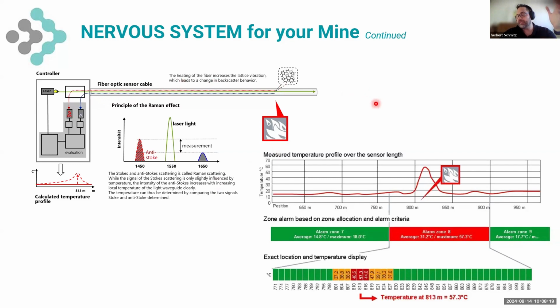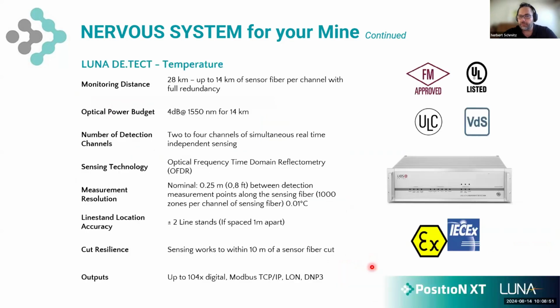And we literally tune into each of the radio stations and we see what the backscatter or reflection is at every point along the fiber optic cable. And we then output that as a temperature profile along the entire fiber optic cable. So the fiber optic cable is the temperature sensor itself. And we can break that down into thousands of zones. And within that zone, we know exactly where that point of thermal energy is.